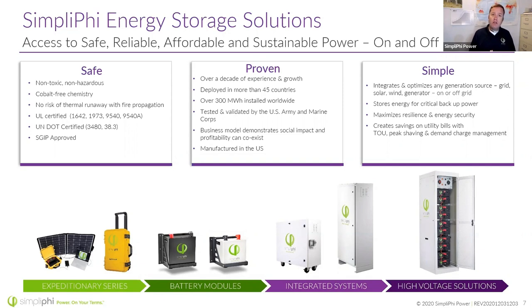So if you're out there to install or purchase energy storage — not just ours, but anybody's — always look for those UL listings. Look for the UL 9540A test report and see if that company is making that report public. We make it public, and I can show you where on our website to find it. UN Department of Transportation 3480 allows us to ground ship these batteries LTL — less than truckload. DOT 38.3 is for air shipping. And for those of you in California, we're approved for SGIP — the Self-Generation Incentive Program.